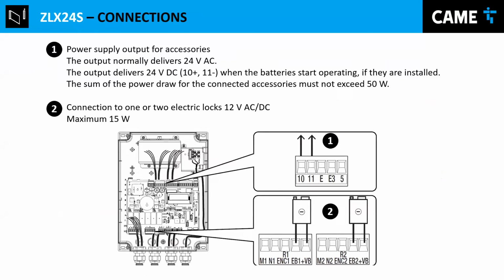So for connections, you have power between pins 10 and 11 - it shows 24 volts AC. When it's in battery backup, that's an accessory, but if you put batteries with a backup, then those 2 pins, instead of AC, become DC, with 10 being positive and 11 being negative. It's not that relevant because accessories can usually receive AC and DC without any problem, but I just wanted to point it out. So remember, pins 10 and 11 always give you 24 volts for accessories, loops, any kind of receiver, whatever you want.